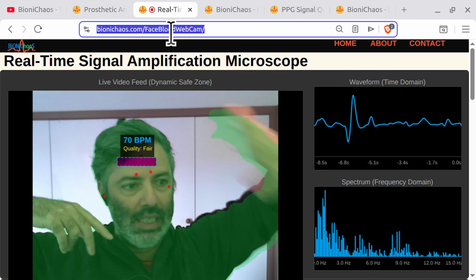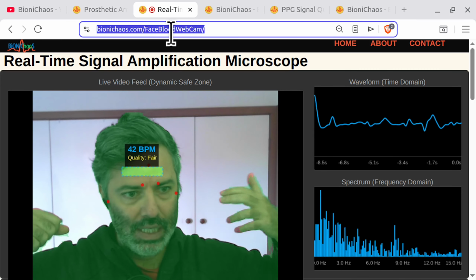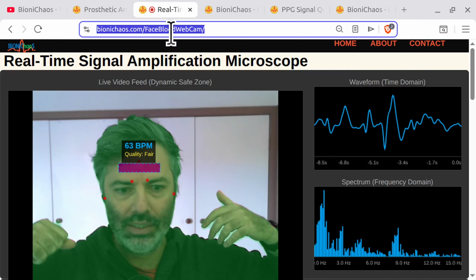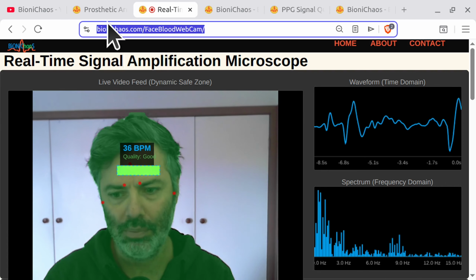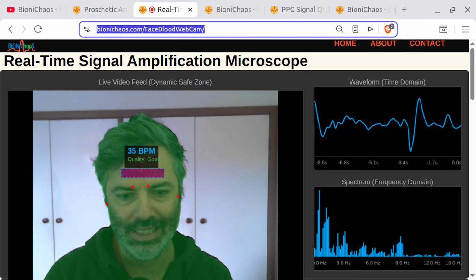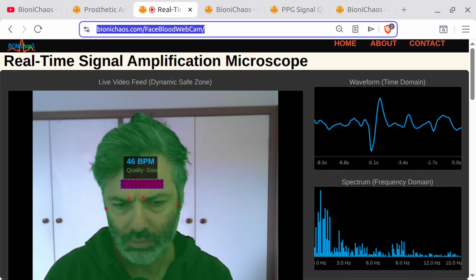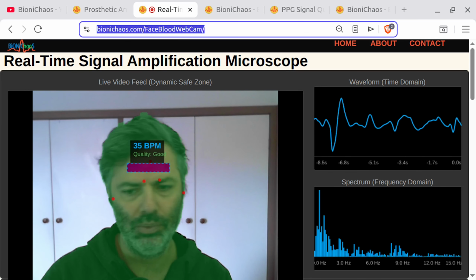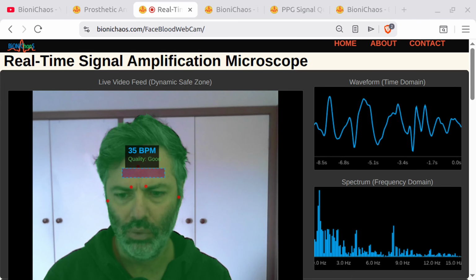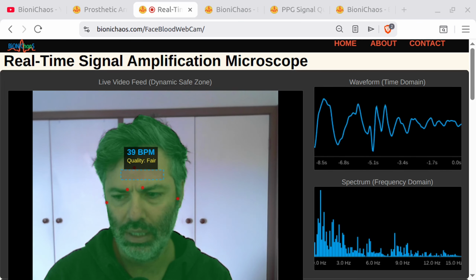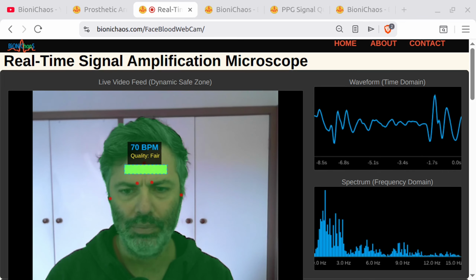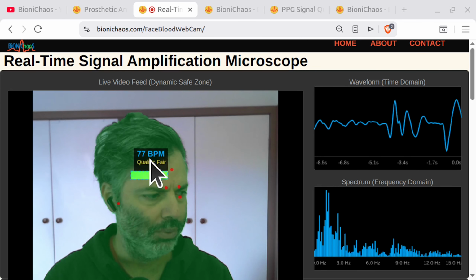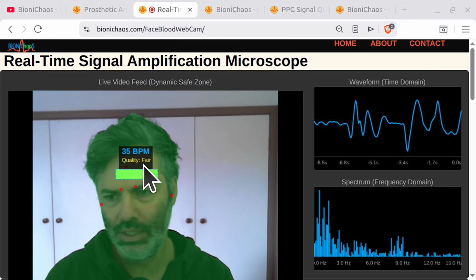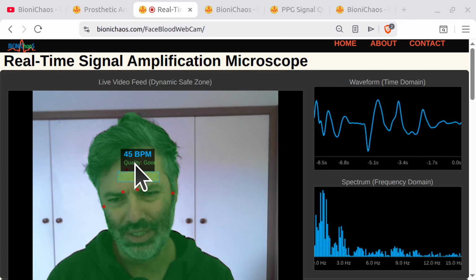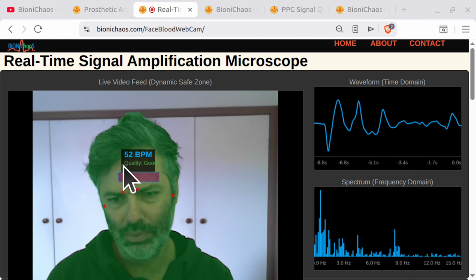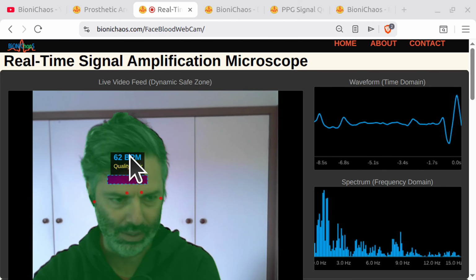So the advantage of the camera is that you don't need anything touching the body. It's remote, right? The disadvantage is that you need to control the light in the room and you have to stay still as much as possible. Well, the longer you don't move, the better the recording is. So now that I'm moving, it's actually not able to. It's showing you the quality of the signal there, and it shouldn't have been indicating good because it's fluctuating, so you don't get a good signal.